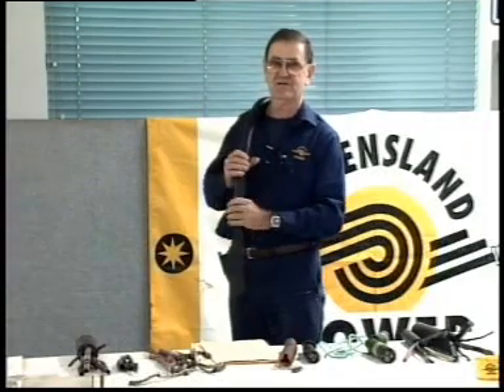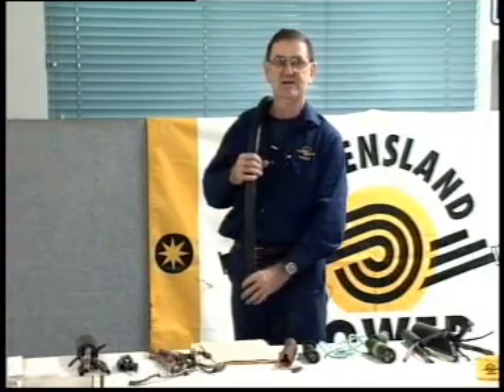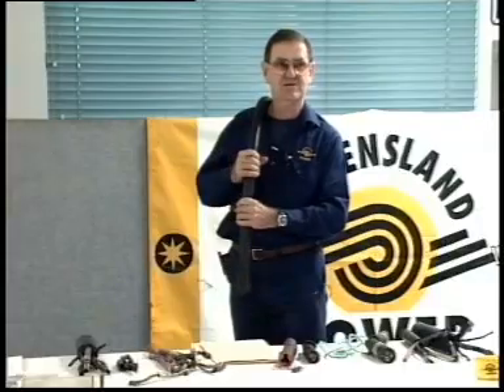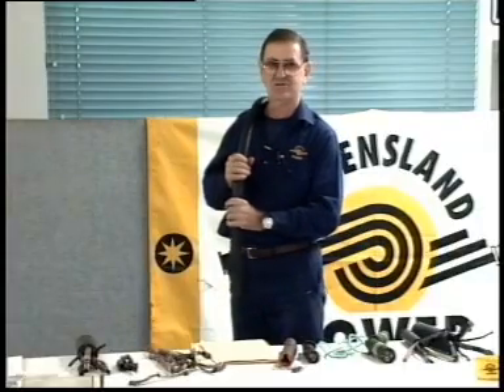The number of repairs in a cable depends on what they are, and it's up to the registered mine electrician where he wants to use that cable. If you had 3 or 4 full splices that were down in the reeling area all the time, or near an anchor point, you would probably want to make sure that you didn't have it there.